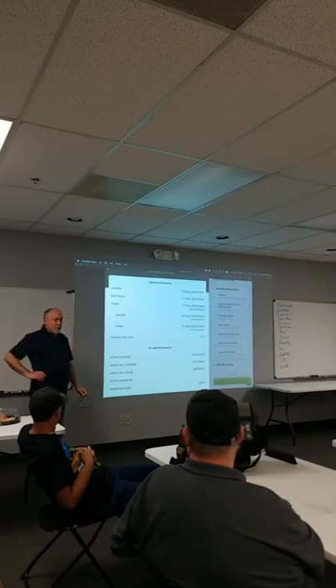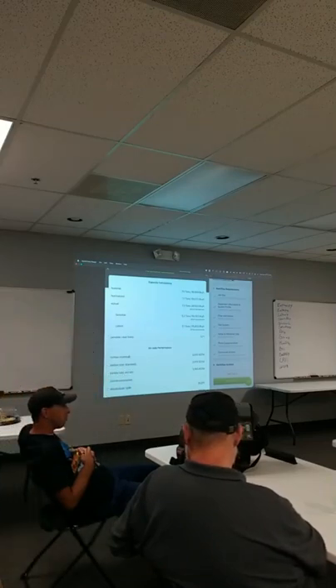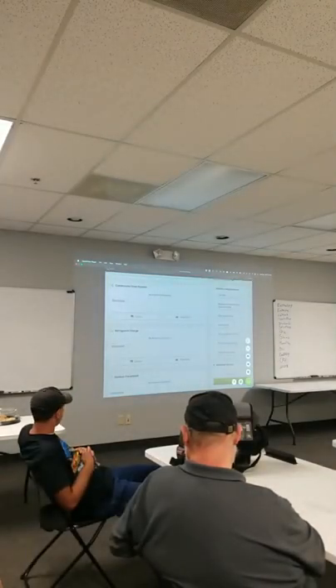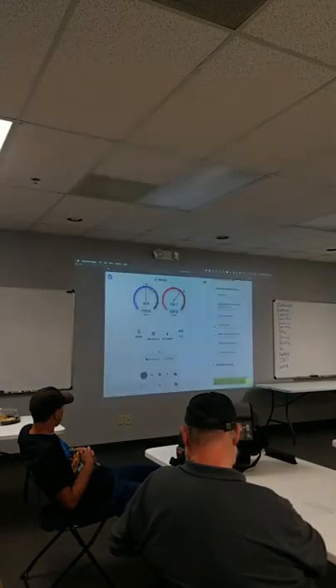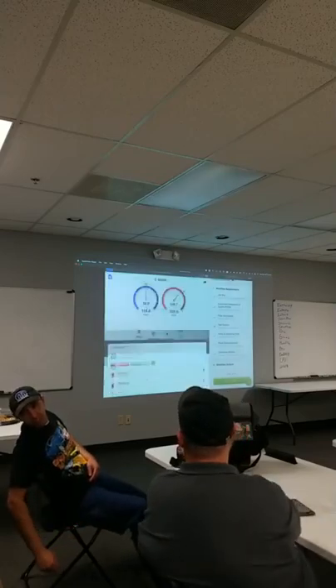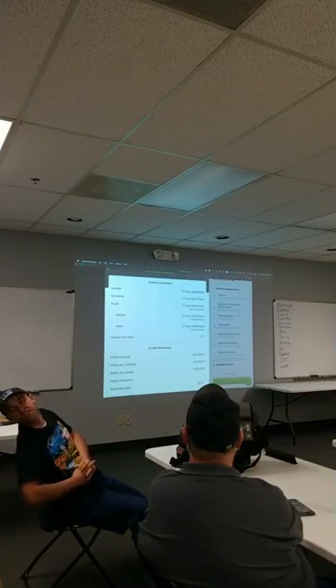You can also have times when you're pulling out 100 or 200% of the latent capacity because the latent load is so high that you can't stop it. We're using everything for latent cooling. So the temperature is not going to drop if you've got 200% latent. It's not going to drop very quickly until it gets that latent load out. Access to your gauges, so if you want to go to the gauges, access to your toolbox, so if you're connecting your probes or whatever. Can you back up to the performance for a second, Jim? Yep. Please. How about scrolling down?